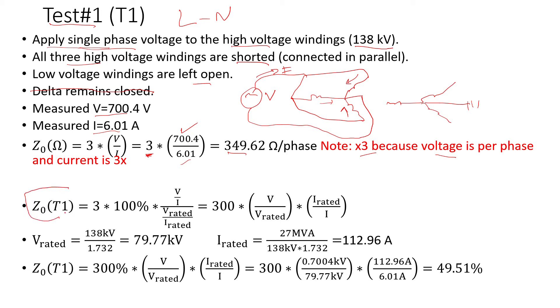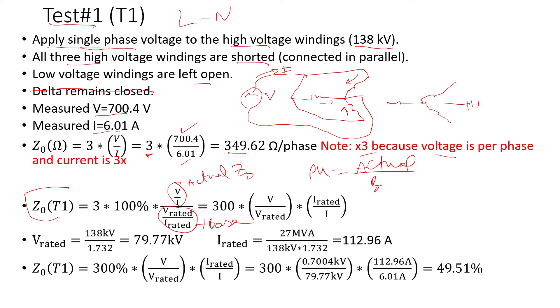The equation to calculate the zero sequence impedance from Test One in percent is: 3 × 100% × (measured voltage / rated voltage) × (rated current / measured current). This is essentially actual impedance divided by base impedance, which is the per-unit definition. I rearranged it as three times measured voltage divided by rated voltage, times rated current divided by measured current.